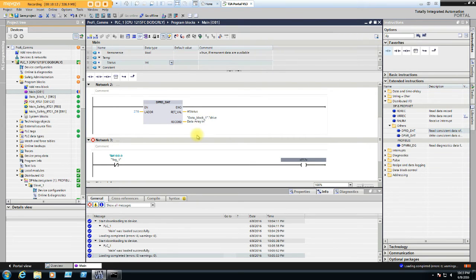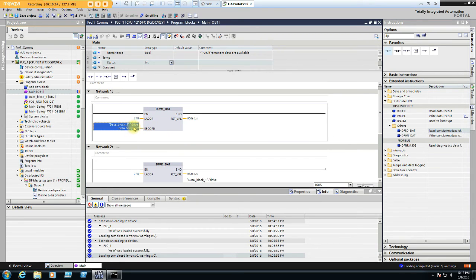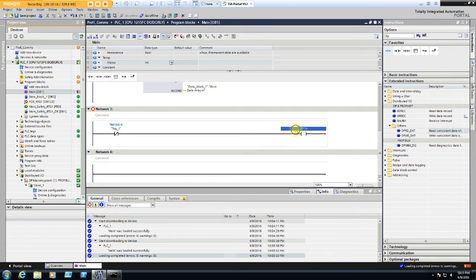Okay, we have to just add a rung here that's going to keep the 10th bit on all the time. This is critical. Your code will not operate the drive without this bit on. You can't set this bit on later. You can't turn it on at will. The drive will ignore command telegrams unless bit 10 is set in the first word, in the command word.